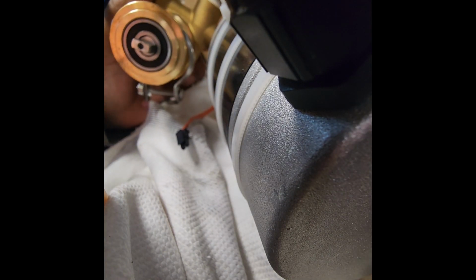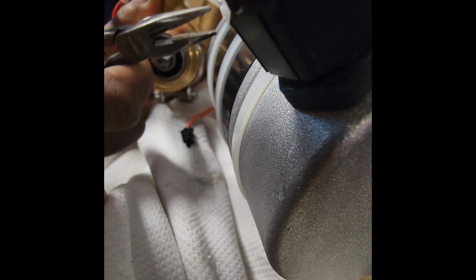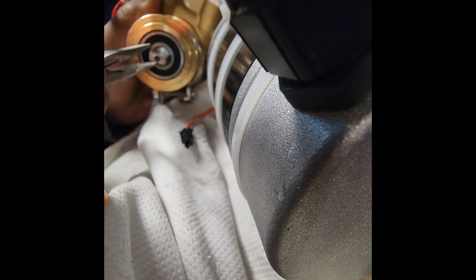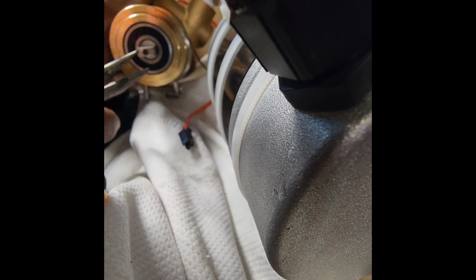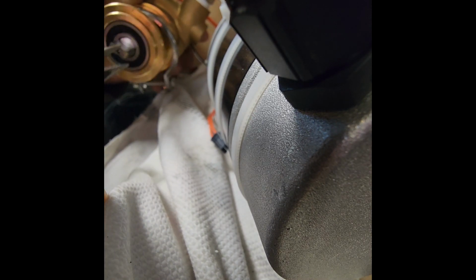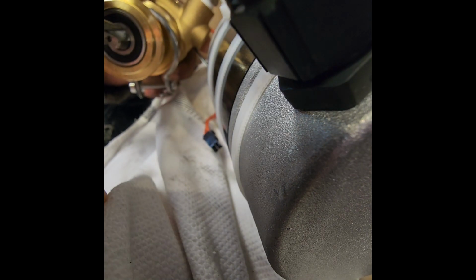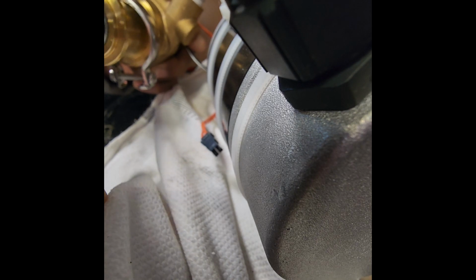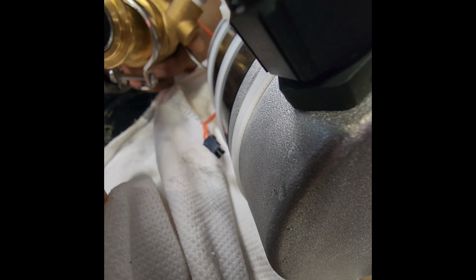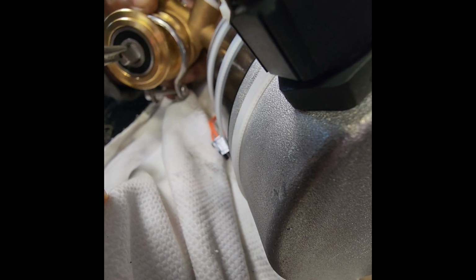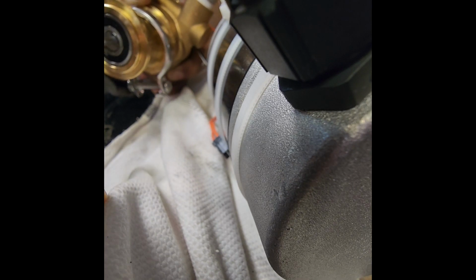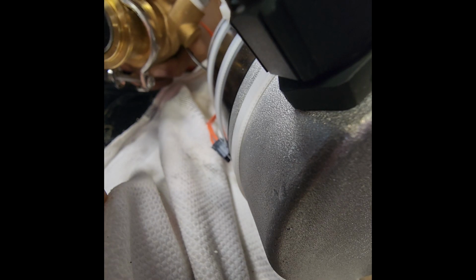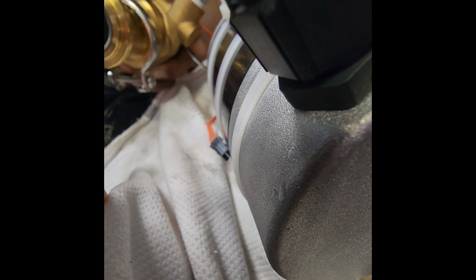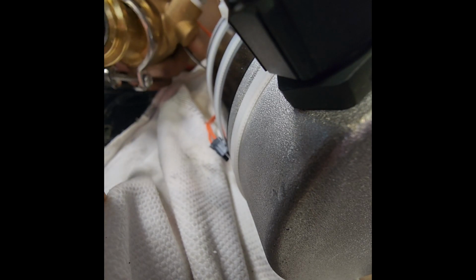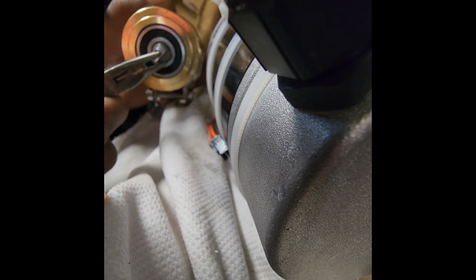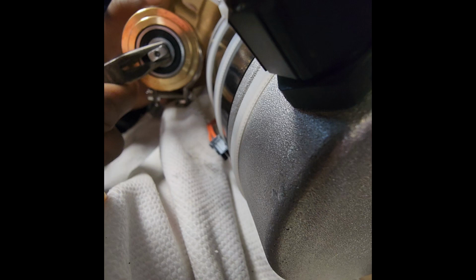Okay, so I got the pump disconnected from the motor. The motor shaft is turning freely, but the pump shaft, while it's turning, is still a little tight. Each time I make a rotation you can hear it click, or at least I can feel it. When I go the opposite direction, clockwise, it seems to get caught on something internally. That could be the issue. I've seen these before where the shaft wouldn't turn at all, but this one is turning, though I do feel a catch within it.